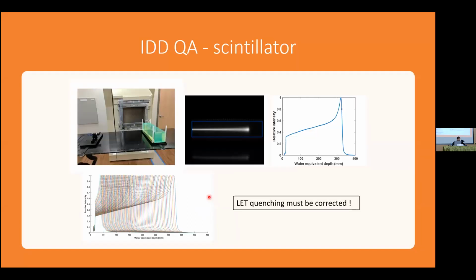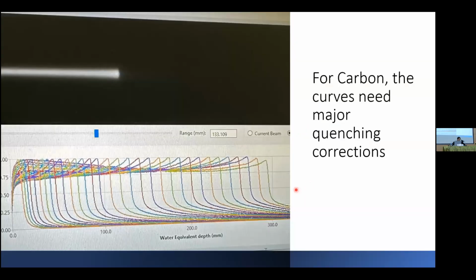Scintillators. So there's a lot of detectors now that are based on scintillator technology. Some more coming out. Maybe by the time you're ready to go live, there'll be some more interesting aspects here. But with these, you're able to do some very interesting measurements. But again, you need to know its limitations. So this is measurements in proton. There is LET quenching, kind of like photons, but you could correct for them. We're just pointing this out because we actually took one of these devices and did it in a carbon center. And you can see that there's a lot of quenching in the carbon center. So again, things that we could go and correct, but just knowing that device, how it's used and what it can actually be used for.